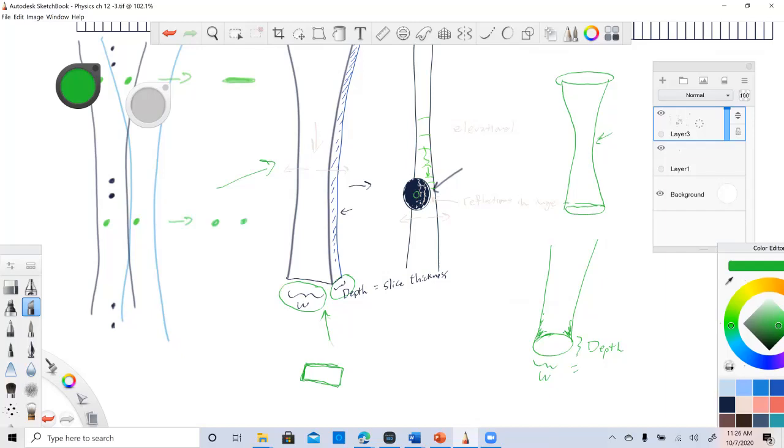Let me just read the next page, because that's actually still a part of the same. What determines elevational resolution in phased, linear, and convex array transducers? These array probes have rectangular shaped active elements side by side. With phasing, the beam is focused or narrowed only side to side in the imaging plane, but not above and below. This narrowing improves lateral resolution, but does not affect slice thickness.